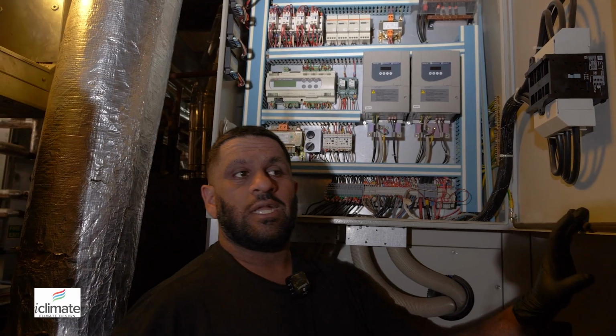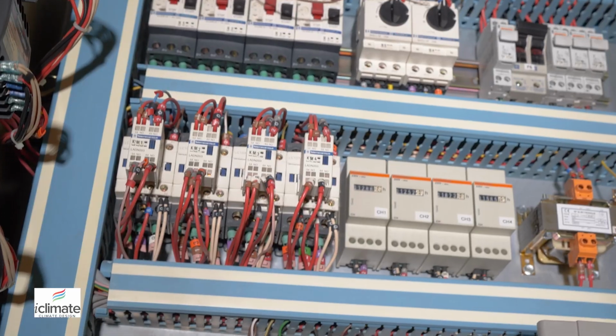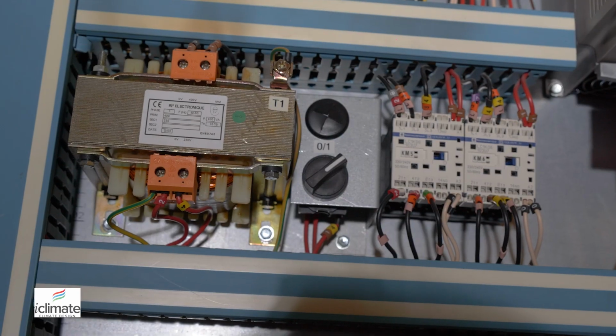If you remember what I said earlier about circuits and diversity, what I found being 30 years in the mechanical and engineering sector is diversification. If you have a system that can diversify its load in as many increments as it can, that's always going to be much more energy efficient and easy to maintain, and also provide a level of comfort that is unrivaled. So the manufacturers have obviously been refining this diversity throughout the last 20 years.